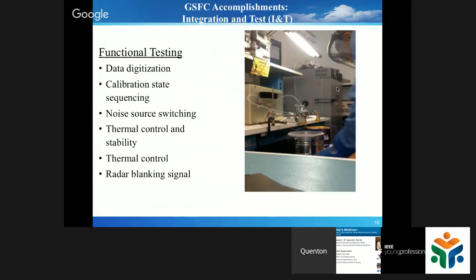And so I mentioned before that we do benchtop testing. We measure the individual components, and the picture to the right is me doing our final benchtop testing. We look at liquid nitrogen and an ambient load. We look at the data digitization. Basically, we run our data into an A to D, and does the resolution look right? If we have a 16-bit A to D, are we seeing 2 to the 16 counts or count steps? And for calibration sequencing, are we sequencing through our calibration loads properly?